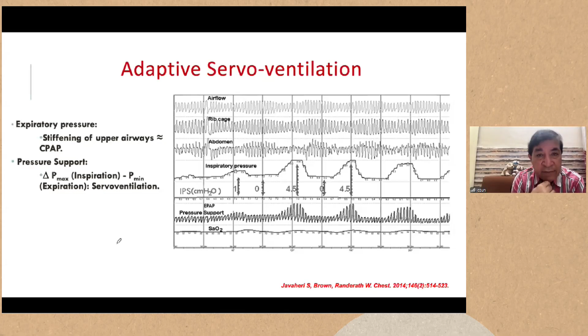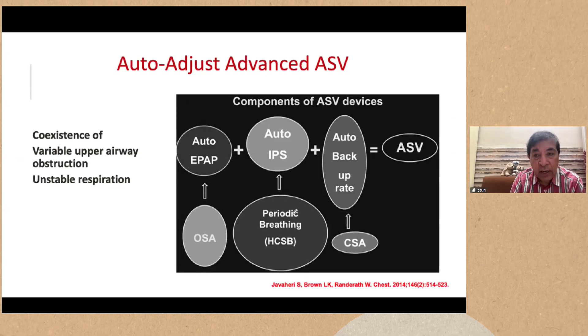Another very important thing in the software algorithm of this device, adaptive servoventilation, is that it decreases minute ventilation by 10%, and with that it causes relative hypoventilation and increases the carbon dioxide level, so that it doesn't go below the apneic threshold. So this is how you give adaptive servoventilation. You give an EPAP to treat obstructive sleep apnea. Then you have auto inspiratory support, which varies from breath to breath and stabilizes breathing. And then if there is a central apnea, you give an auto backup rate. This combination is what is called adaptive servo ventilation.